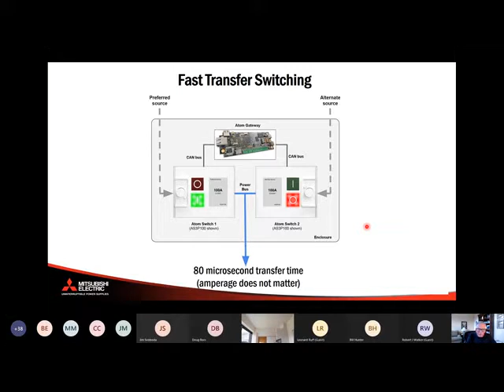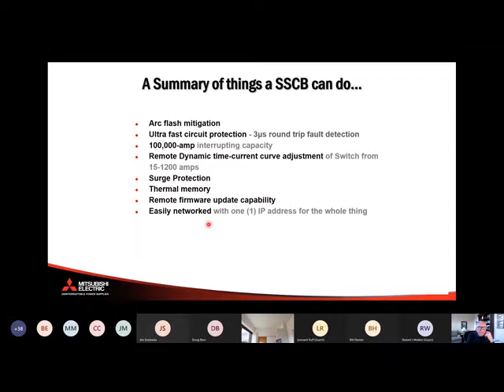So to summarize, these solid-state breakers: arc flash mitigation, ultra-fast circuit protection, 3 microsecond round-trip fault detection. I think it's up to 200 KAIC interrupting capacity - this is an old slide, I picked that up when I heard the Atom Power guy talk last week. They're up to 200 KAIC, with remote dynamic time current curve adjustment, fully selective trip coordination at your fingertips, surge protection, thermal memory, remote firmware update capability, and easily networked.